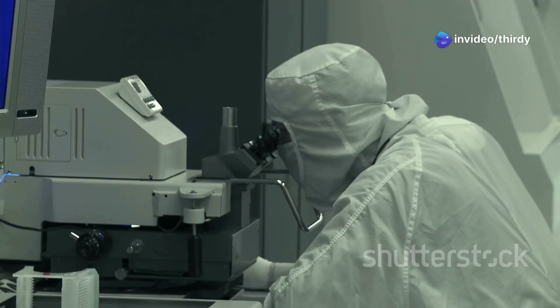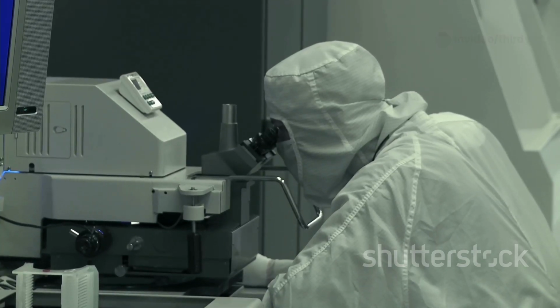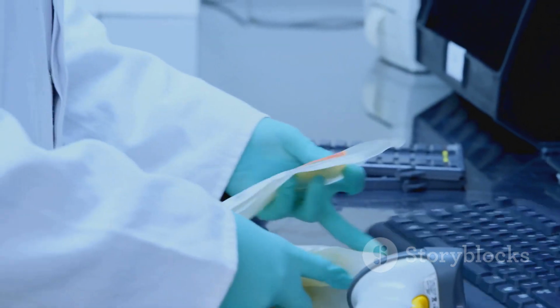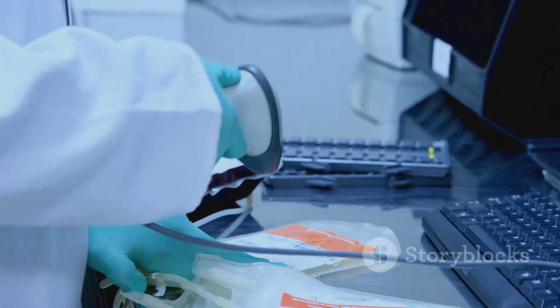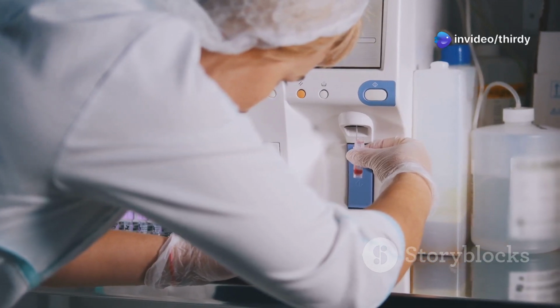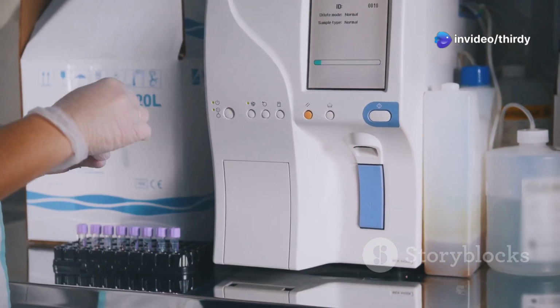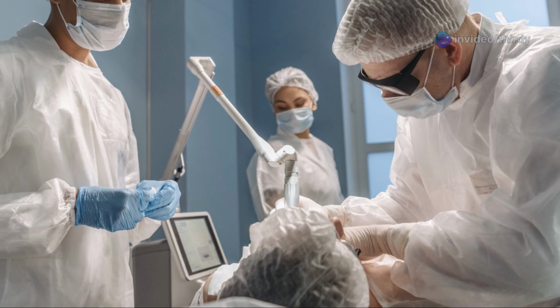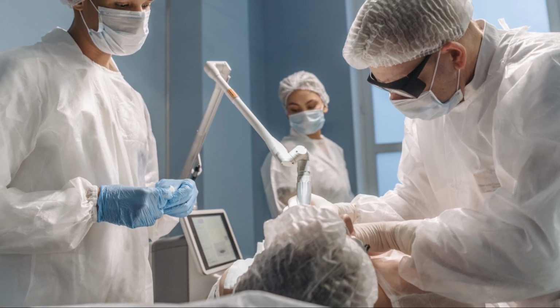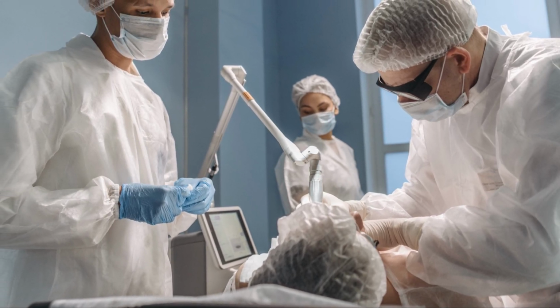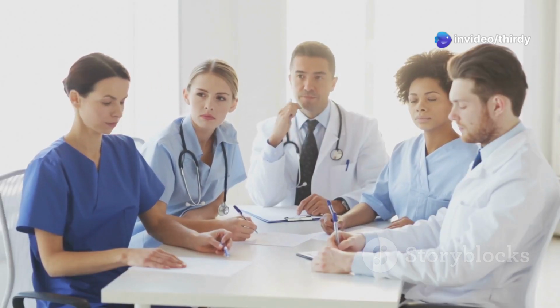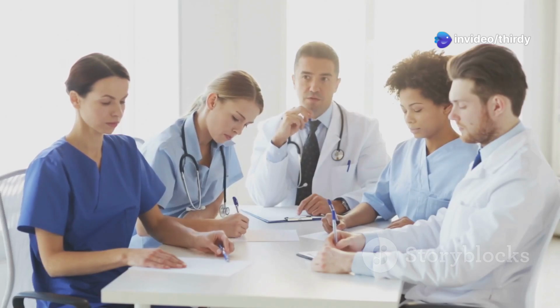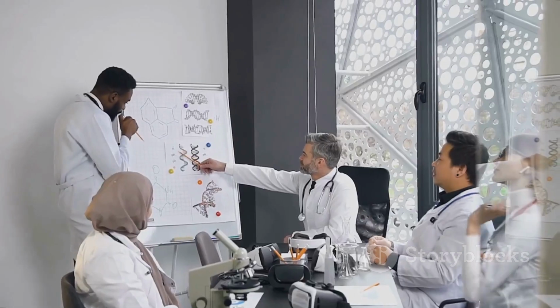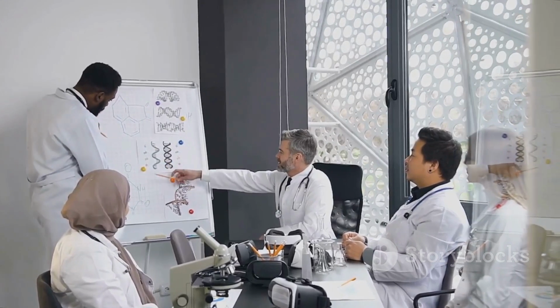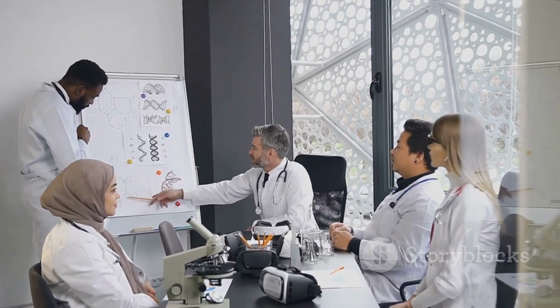Building accountability also involves robust quality assurance measures. This means implementing rigorous tracking systems for surgical instruments, allowing a hospital to trace any tool back to the specific patient, the sterilizer load, and the technician who processed it. Regular audits of procedures, unannounced inspections, and monitoring of sterilization process indicators are crucial. When errors are found, the focus should be on understanding the system failure that allowed the error to happen, rather than on blaming an individual. By analyzing near misses and errors, we can identify weak points in the process and implement stronger safeguards to prevent them from happening again.